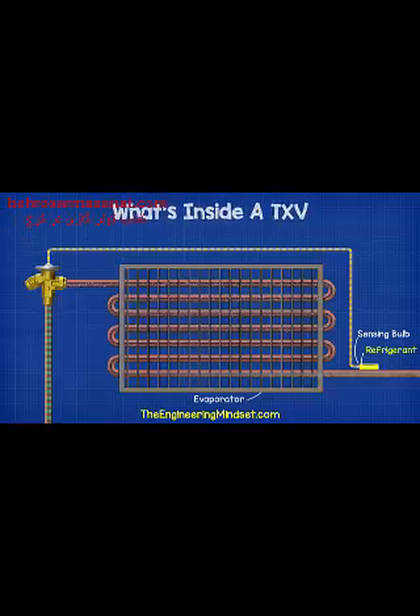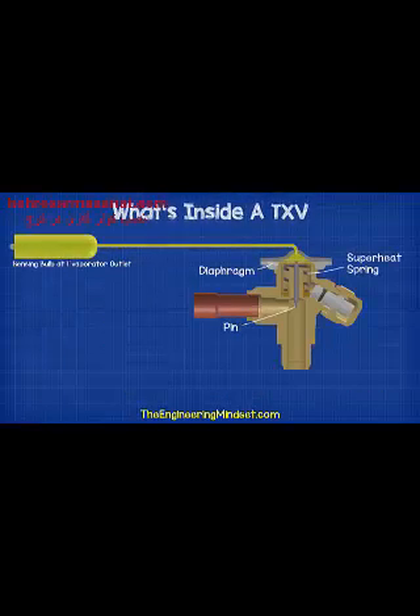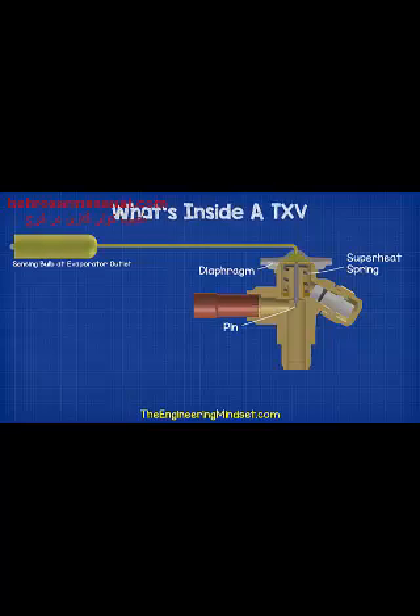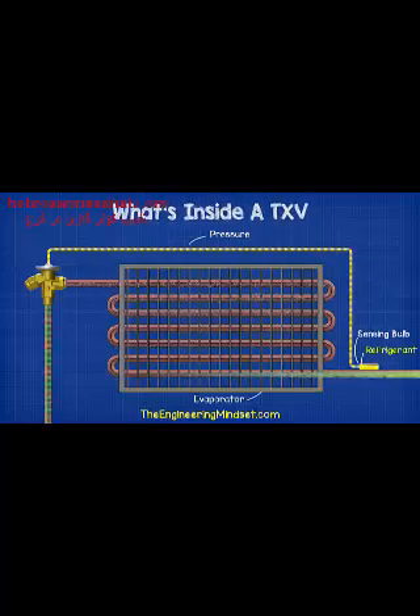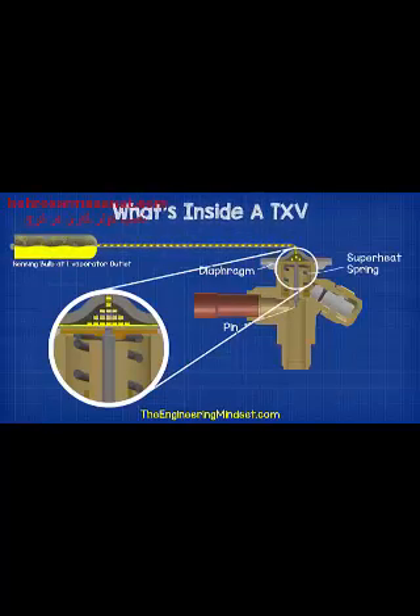As the cooling load on the evaporator increases, the superheat increases at the evaporator outlet. Because the sensing bulb is in direct contact with the pipe at the evaporator outlet, the thermal energy transfers and causes the refrigerant inside the sensing bulb to expand and boil. Because the sensing bulb, capillary tube and the chamber are all hollow and are a sealed system, as the refrigerant expands and boils, it causes the pressure inside to increase. This pressure travels along the capillary tube and makes its way to the chamber above the diaphragm. As the pressure increases, it pushes down on the diaphragm and this pushes down on the pin.